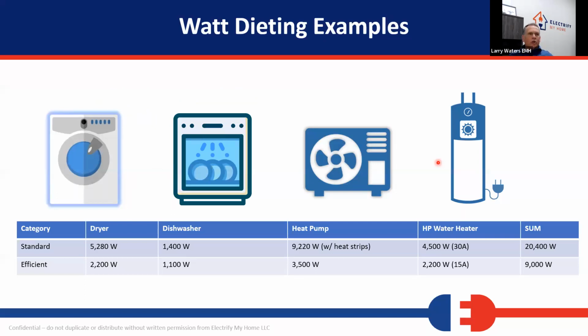So we talked a little bit earlier about the watt diet. Let me just do a time check real quick. Okay. We talked a little earlier about the watt diet. And so if we look at some things like standard versus efficient on a couple of different systems, if we put in a standard dryer, we need 5,280 watts for those, pretty much average. If we put an efficient dryer in, like a heat pump dryer, we can get that load down to 2,200 watts. When we're figuring in our loads, when we're doing our panel load calculation, all of these cuts really help.